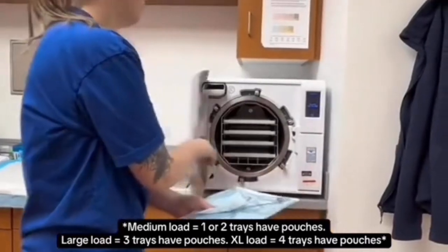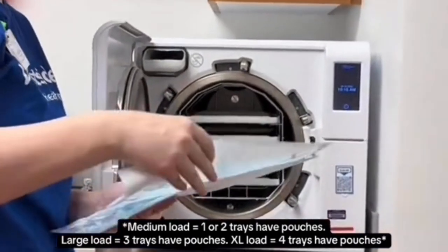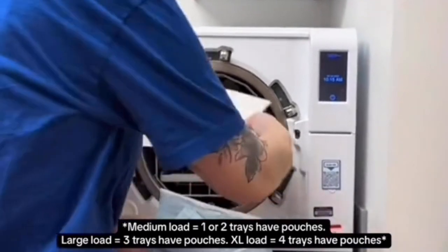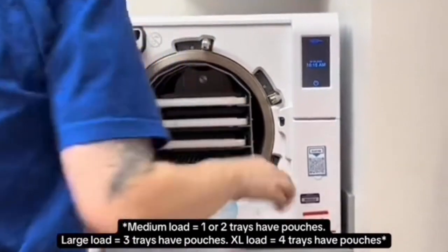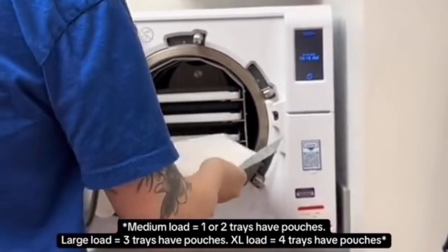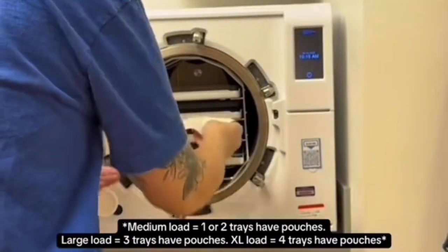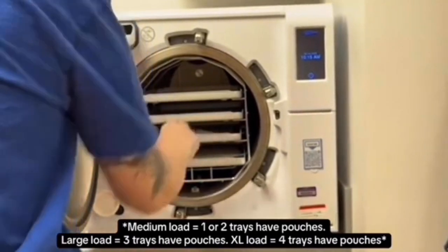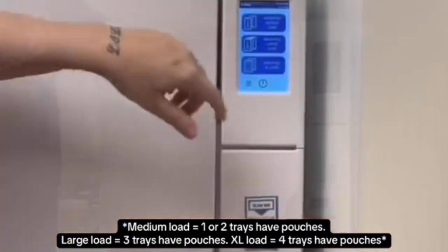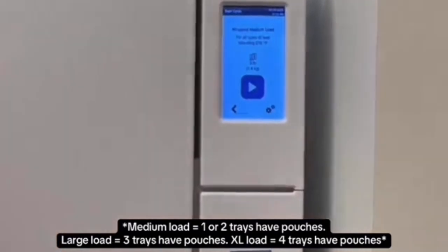Put the pouch on the tray in the autoclave with the paper side up, making sure the pouches do not overlap each other or the tray. Place the process challenge device on one of the two middle trays, then choose the right cycle.